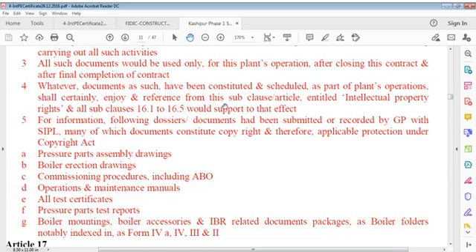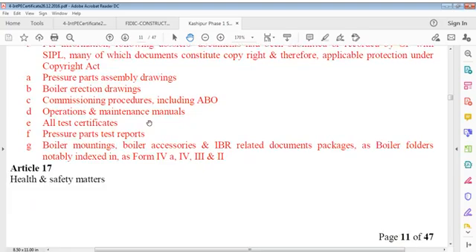Comment 5: for information, the following dossiers and documents had been submitted or recorded by the contractor with the employer, many of which documents constitute copyright and therefore enjoy applicable protection under the Copyright Act - pressure parts assembly drawings, boiler erection drawings, commissioning procedures including ABO, operations and maintenance manuals, all test certificates, pressure parts test reports, boiler mountings, boiler accessories, and IBR related documentary sketches, packages, and boiler folder.